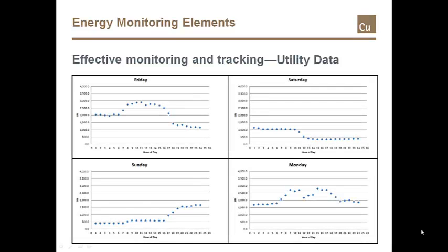This kind of data allows monitoring of power usage during hours when production occurs and at times that no production may be occurring. In this example, covering Friday through Monday, including hours when no production occurs, it may be seen that significant power, roughly 1,000 kilowatts, is being expended on Friday night through Saturday morning, while almost 500 kilowatts is used during Saturday afternoon until Sunday evening, when machinery is activated and prepared for the Monday production cycle. This kind of data may be used to modify operational procedures to minimize unnecessary energy consumption.